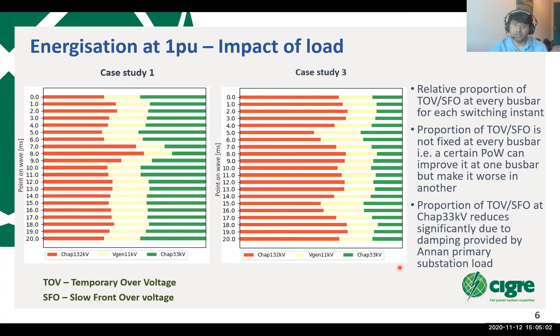The other takeaway from this one is that if we compare these two figures, where we know that case study 1 and 3 are exactly the same, only in case study 3, one of the primary substations was energized before energizing the transmission circuit, we can see that the proportion of these green horizontal plots is much lower than what we see in case study 1. This means that if we have a primary substation or a demand connected in the network, that has a positive impact on the overvoltage at a bus bar. Later on, when we look at further results, we will find out that the impact is not uniform and it has the highest impact on the bus bar which is closest to the demand connected.